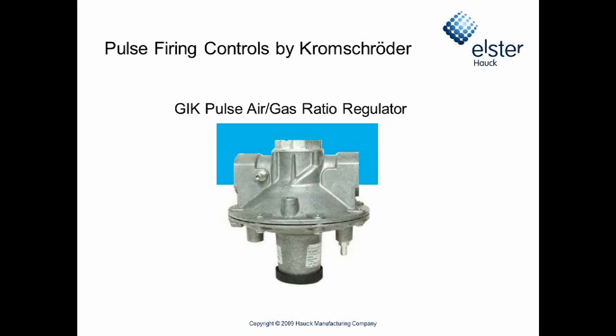The Kromschroder pulse regulator is specifically designed, again, for pulse fire applications. As the burner goes from high to low or high to off, the diaphragm is balanced, so it is designed not to oscillate. So you won't get a bouncing signal if you pulse burners too quickly.